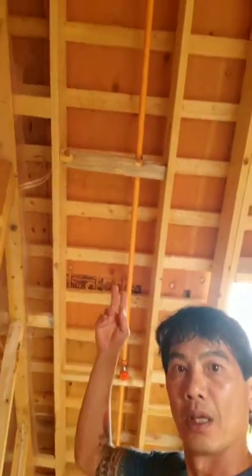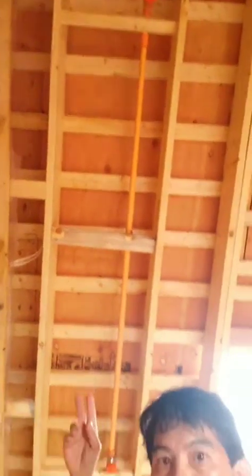Here they are above me on an 8/12 pitch. Now you gotta account for slopes. Once it gets over 8/12, you gotta account for a different sprinkler head. A commercial head, a Globe 5.6 is probably what I would use rather than a 4.9. But we're at 8/12, so we can still use 4.9.